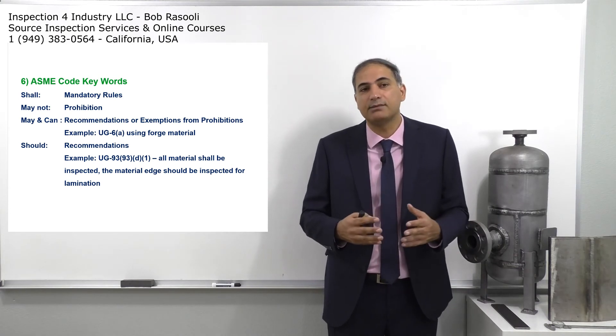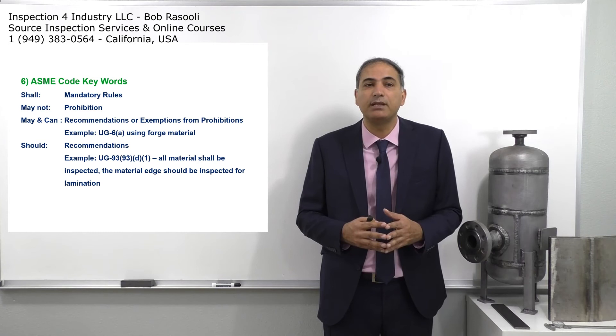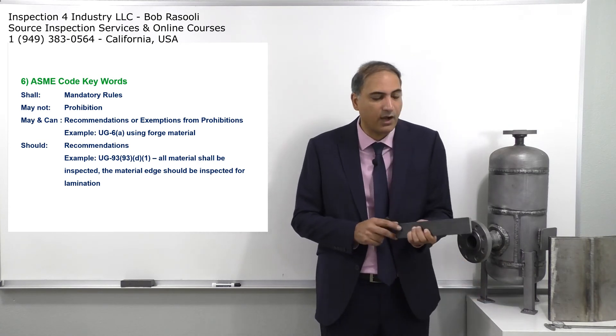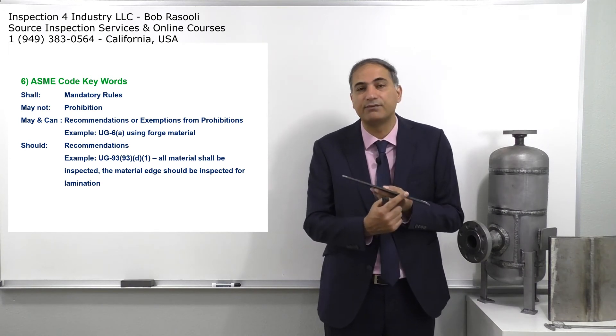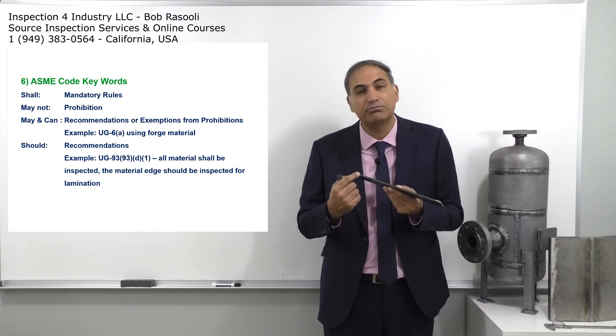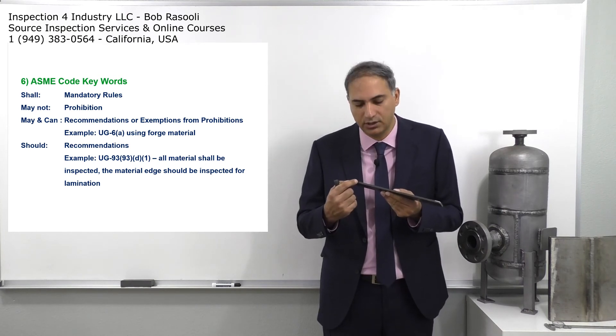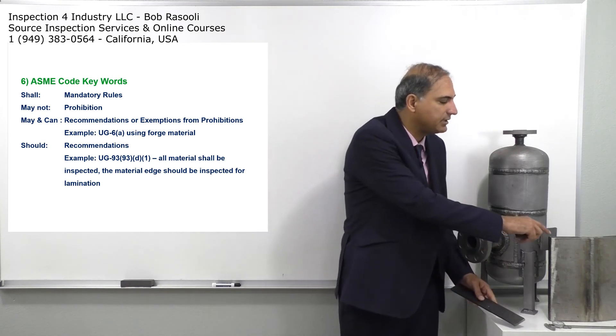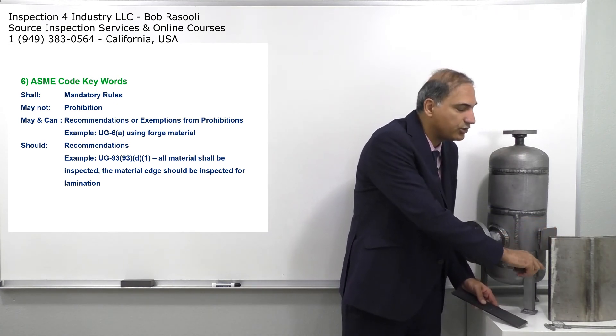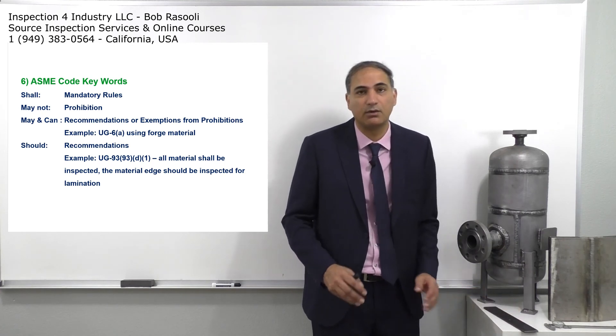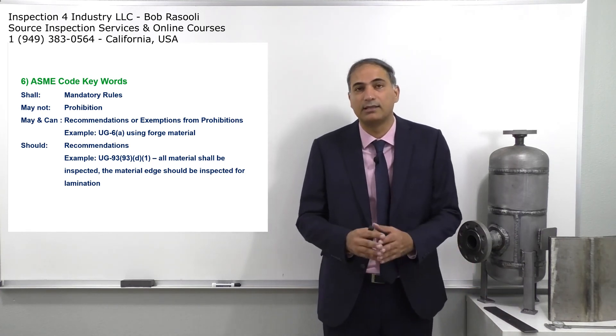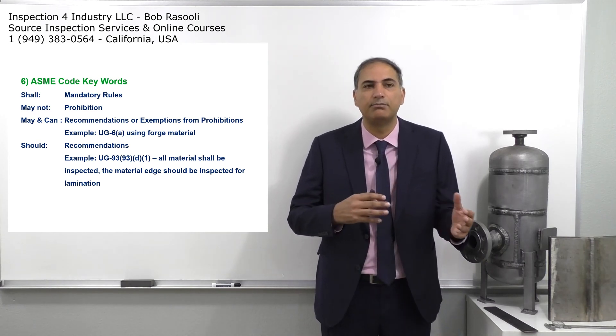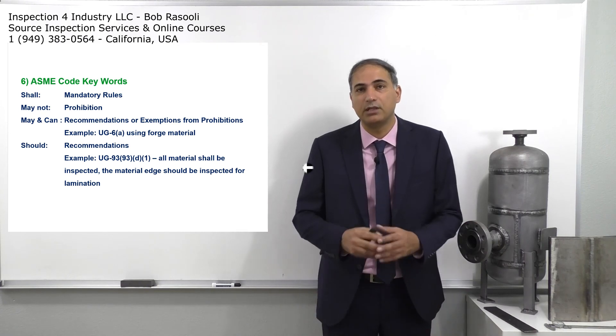But the next sentence says the material edge 'should' be inspected for lamination. If it's SA-516 Grade 70 plate, the word 'should' means it's a recommendation — we should inspect the edges to make sure there is no lamination, but it's not mandatory like 'shall.' This is the key difference between 'shall,' 'should,' 'may not,' and 'may' or 'can,' which we need to know.